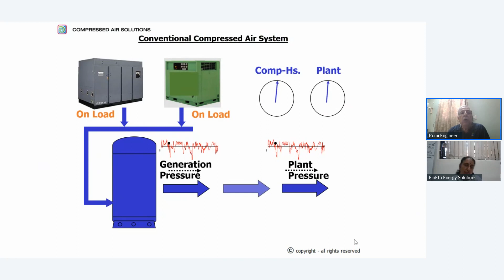This is what happens, and this is again the data we're getting from data analytics. We don't have to run around or go check things manually. Here, because the setting was not proper, you see there are 3 compressors in operation, wastage of energy, load and unload, load and unload - you see that graph going up and down.